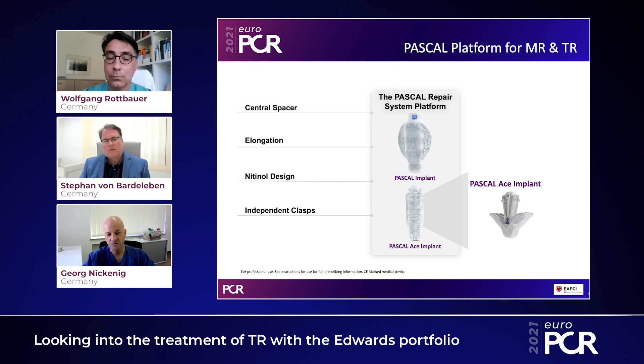There is a central spacer in between, which is there to reduce the residual central jet of regurgitation. You also have the possibility to elongate the whole system to exclude entanglement into chordae. These are the most important features of the device — particularly its flexibility and non-entanglement in the tricuspid apparatus.